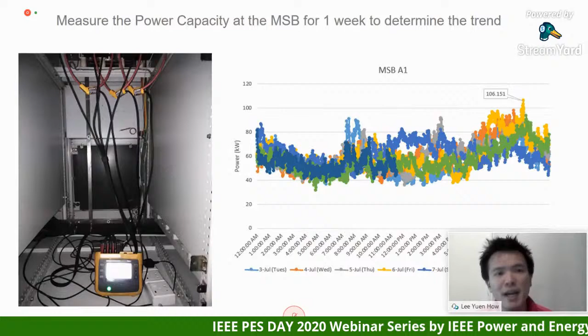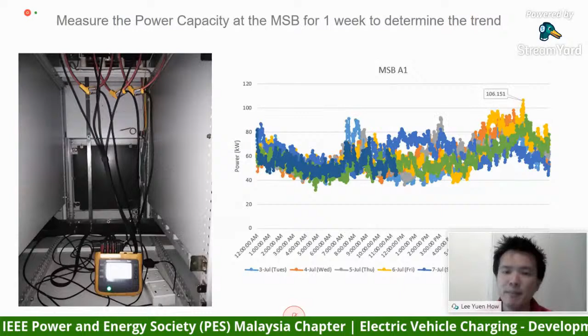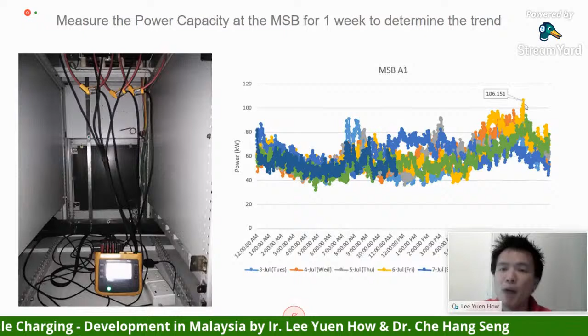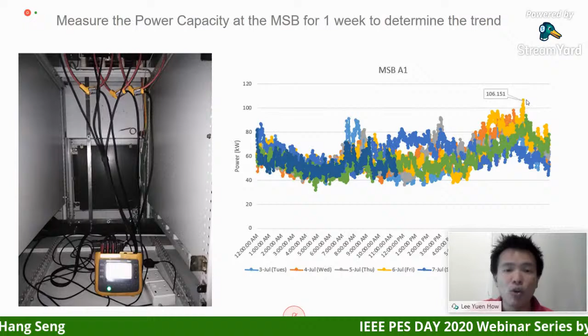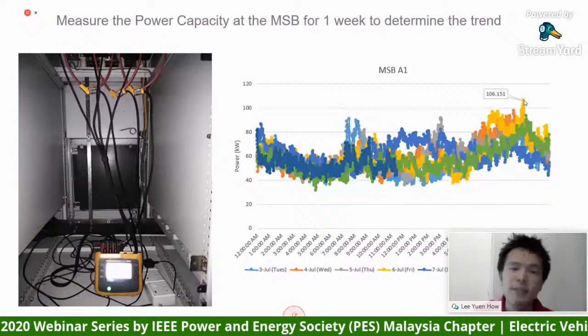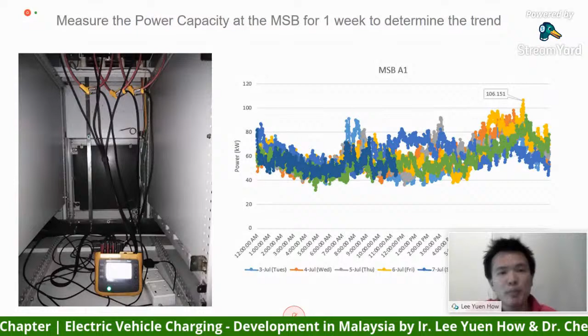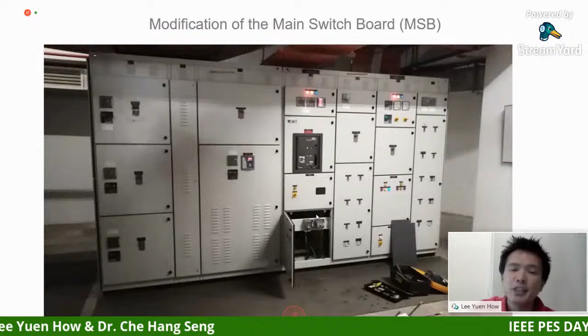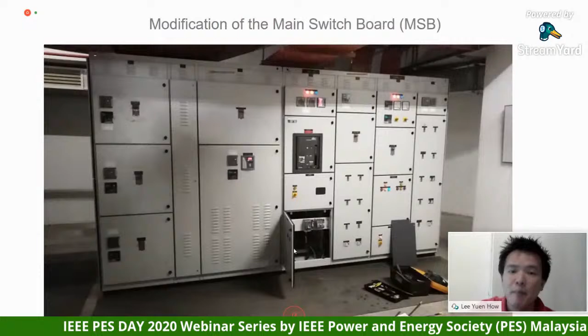But first, if you are an existing condominium or apartment, you need to measure how much excess power capacity you have. Once you determine the highest peak of energy or power used, divide it by the total number of units available. Then you will know how much power can be allocated to each resident. Once we get this power capacity measurement from the main switchboard, we can modify it to cater for an additional breaker to pull for the new sub-switchboard EV.